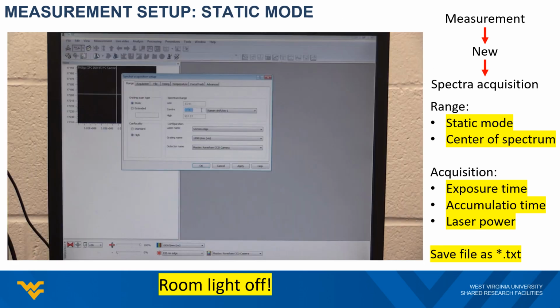If you choose Static Mode under the Range tab, you will only need to choose the desired center wave number of your measurement, while the total spectral range is determined by the acceptance spectral range of the grating, which is calculated automatically. Usually, you only choose this mode if you need to observe specific Raman peaks at known positions. For example, when you measure a silicon calibration sample to confirm the existence of the 520 inverse centimeter peak.